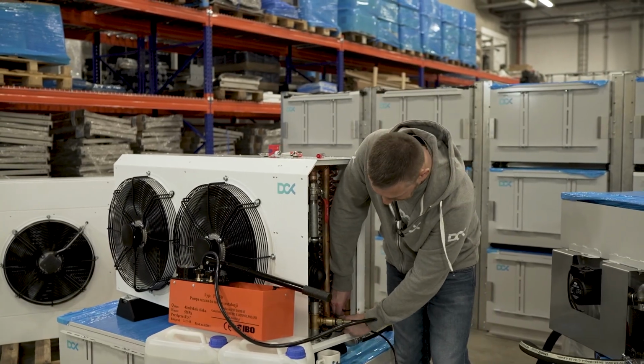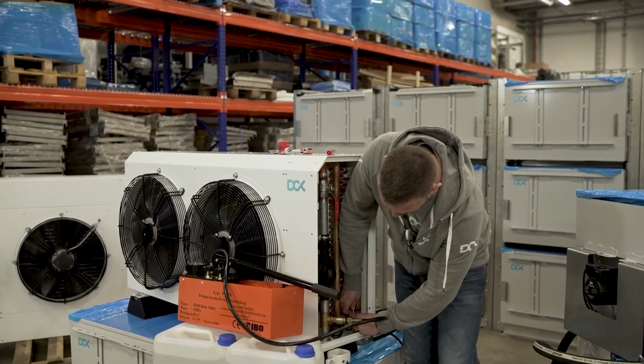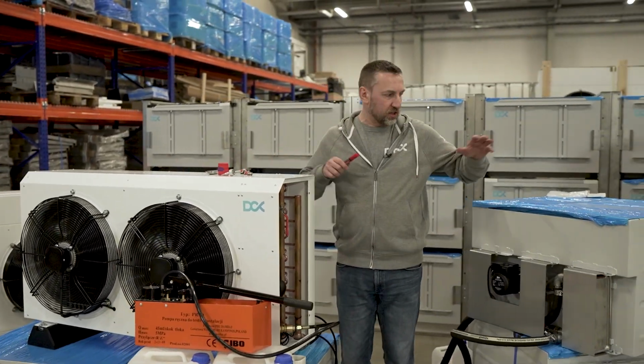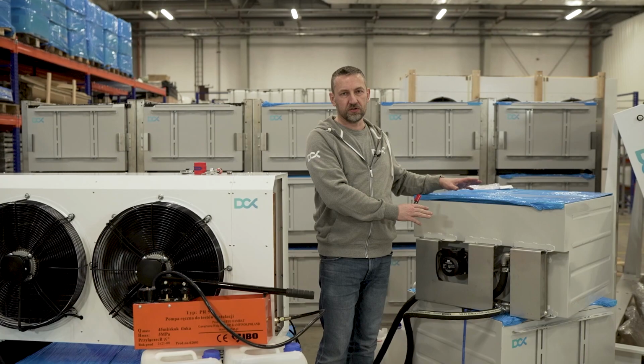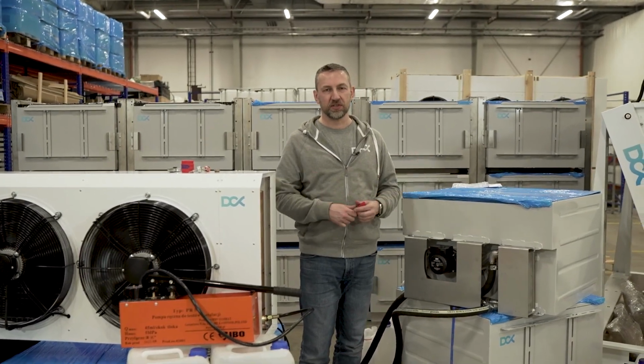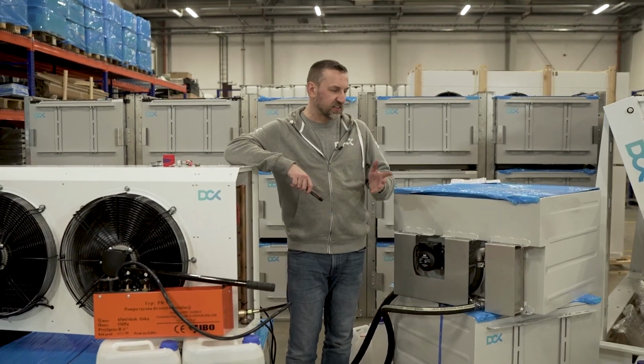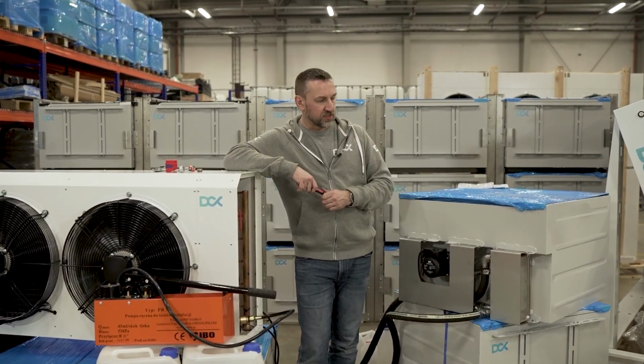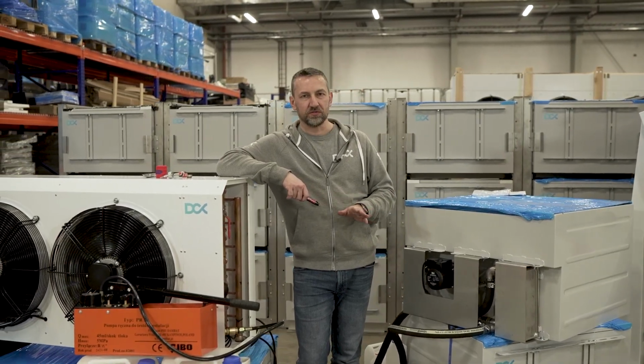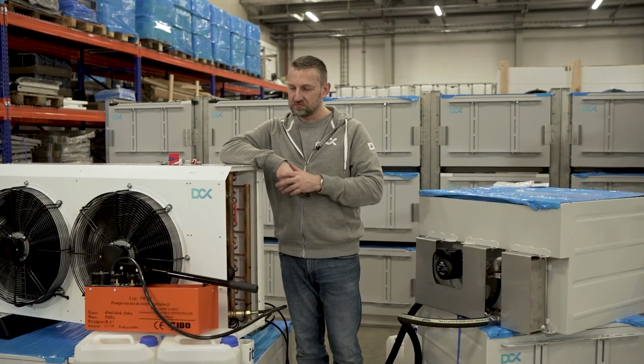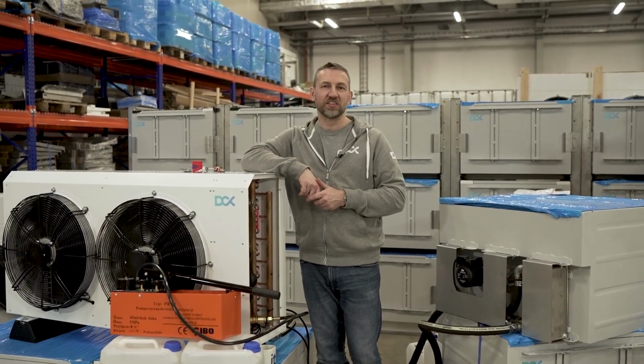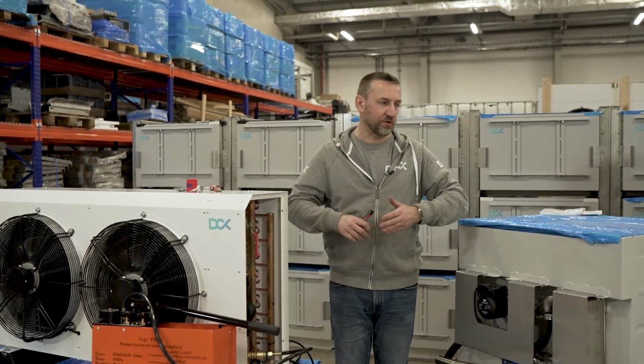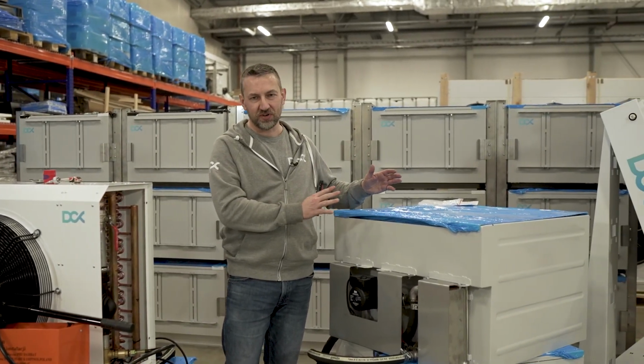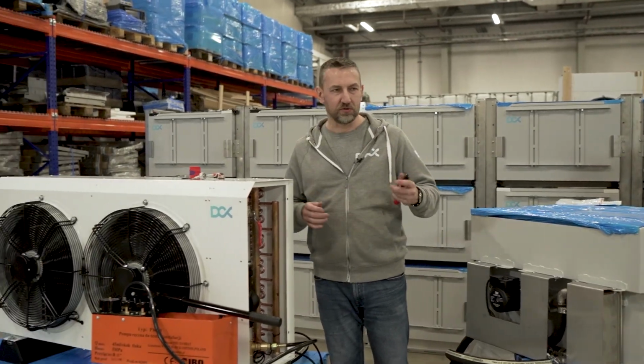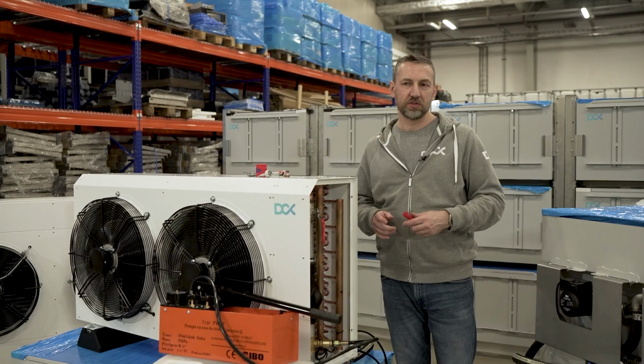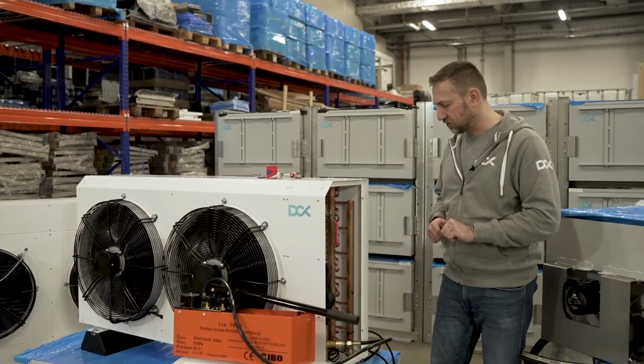So please compare that with the noise of the 12 miners which fit that enclosure, running at 89 or 90 decibels, or compare it to the noise of 8 Antminer S19s, which we have here. That's, let's say, no comparison at all. That's unbearable, and this is a pretty quiet AC unit by comparison, right? So that's the comparison, and that allows you to run your operation, with 40 kilowatts of heat transfer, in an industrial, commercial, or residential area. That should be just fine for most occasions.